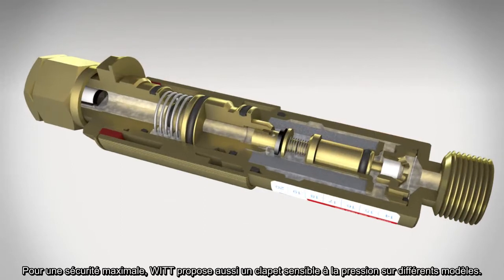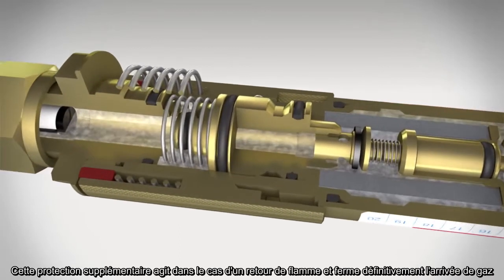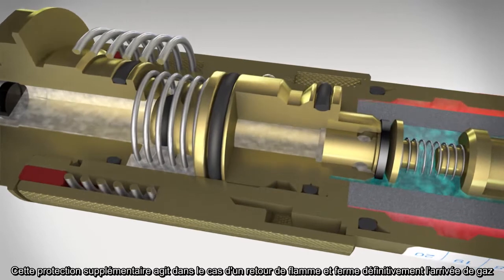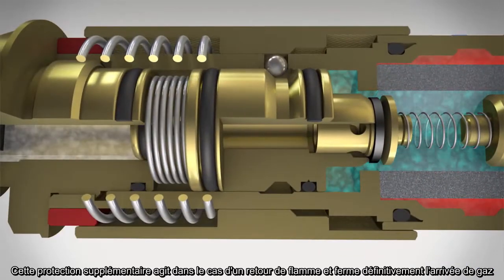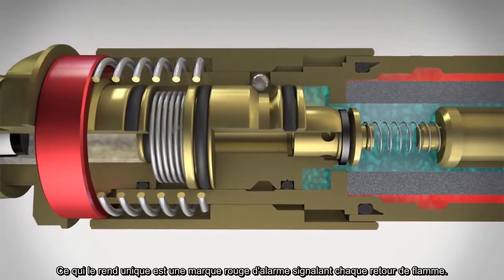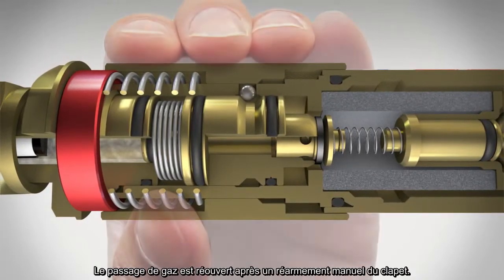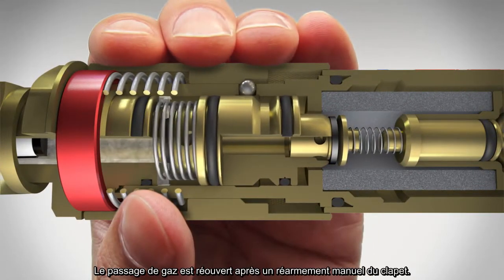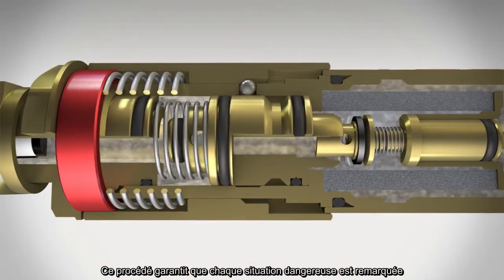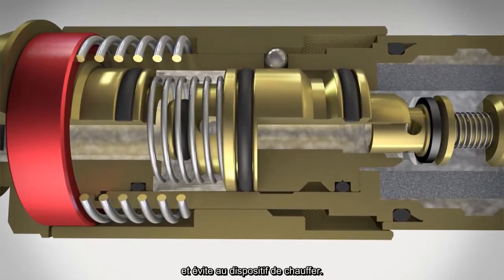For maximum safety, WITT also provides a pressure-sensitive cutoff valve for various models. This additional protection element activates in the event of a flashback and interrupts the gas supply permanently. A red alarm indicator makes every single flashback visible. The gas flow is only opened again after manually resetting the cutoff valve, ensuring that no dangerous situation remains unnoticed and preventing the safety device from potentially heating.